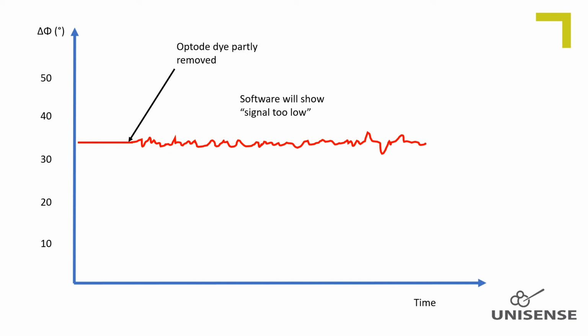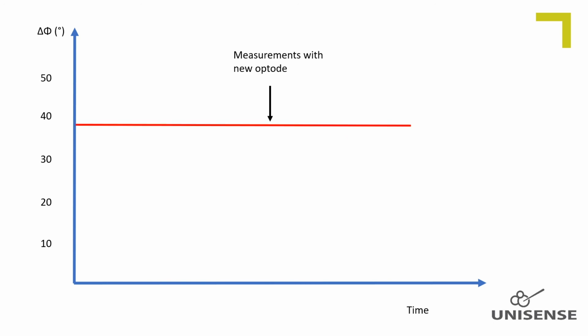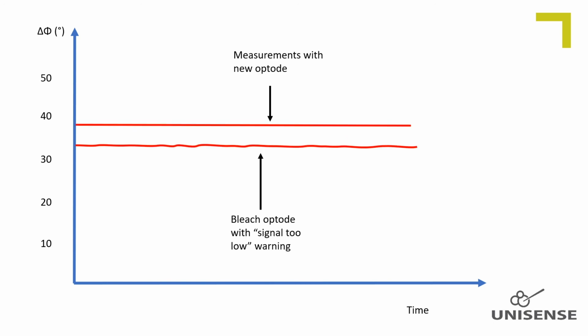An Optode which is associated with a signal too low warning might still be sensitive to oxygen, and it is up to the user to judge whether the data quality is sufficiently good to be used. The cost of shipping, reactivation and recoating the fiber is so high that we do not offer repairing Optodes which lack dye. When an Optode is end of life due to bleaching, the signal too low indicator is turned on in the software.